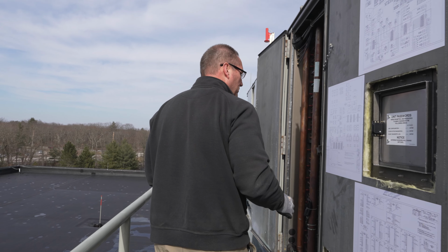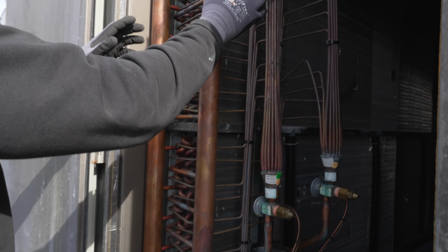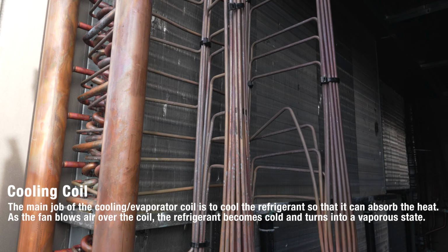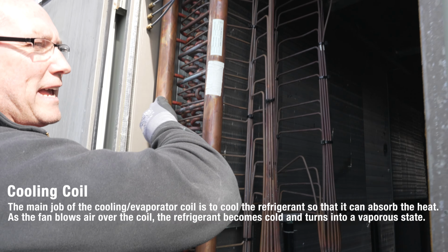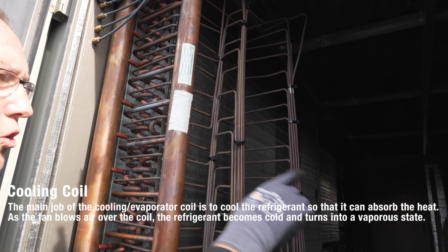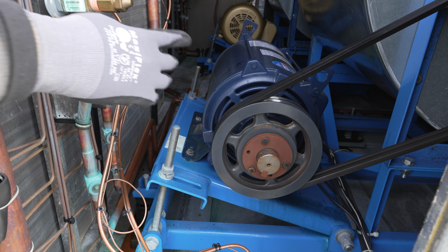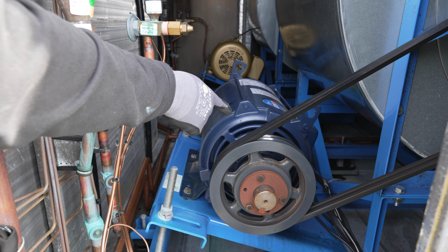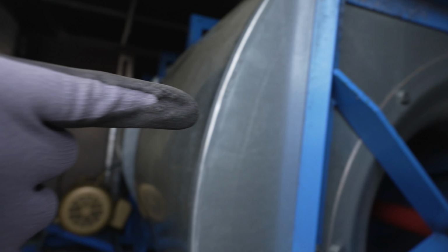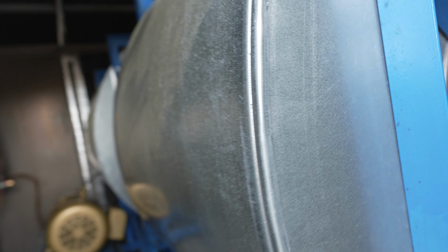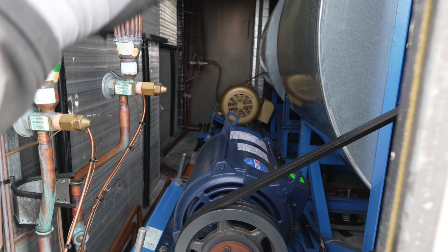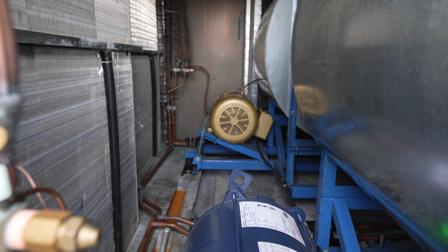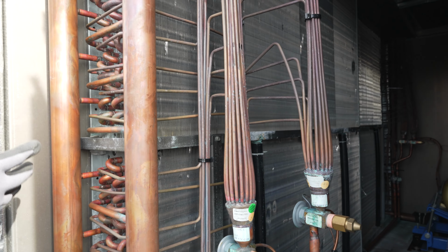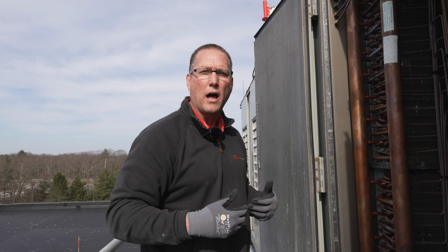So if we come over here, we enter the evaporator section. This is your cooling coil. Air, like the condenser, no different, is being drawn in from the other side of this coil through these supply fans here. With these supply fans, we need to make sure that the bearings are greased, not only here at the motor, but on the shaft bearings as well, right behind that wheel. So there are bearings on each side, and it looks like there are 2 motors in this unit. We have to make sure these motors are in good shape too, because the cooling coil, to be honest with you, is like the human body's lungs. You need that air going across the lungs to make sure that everything else in the system is going well.